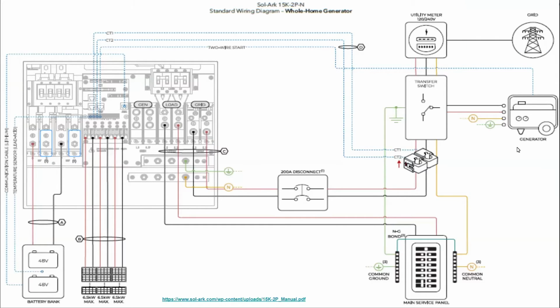I think it makes a lot of sense to have a portable generator or a manual start generator process to avoid all of these design considerations entirely. I know we want to give our customers everything, but do you really want to automate when you've already got an automatic home energy backup system? Do you want to automate the additional step of having the generator turn on automatically? I think there's a pragmatism to say, when the batteries drain all the way down to their minimum state of charge, even though you have a battery and a solar generation station already on site, if you still run out of juice, require the customer to press a button just so that they know what they're doing. They're not going to learn anything about their system until they press that button. So try not to over automate everything.